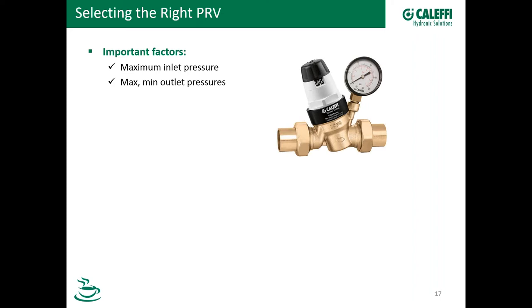We also need a minimum usable pressure because fixtures require a certain minimum pressure to function properly. Regarding flow rate, we need to know the maximum flow rate — this is determined by a fixture calculation procedure. We also need to know the minimum flow rate because we don't want to specify a valve that is too big. An oversized PRV is going to be unstable if you're trying to operate it near the closed position, and if you try to operate a valve near closed for too long, you'll see problems like premature wear on the seat.